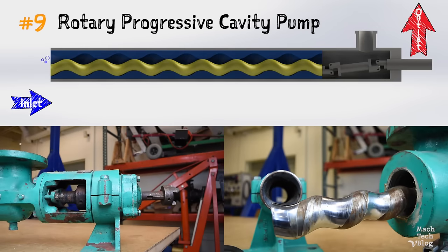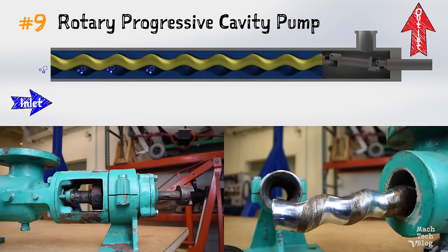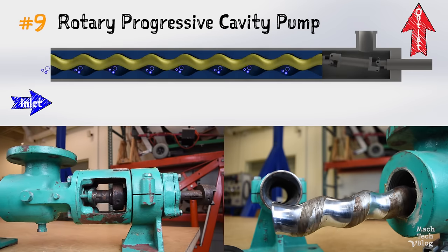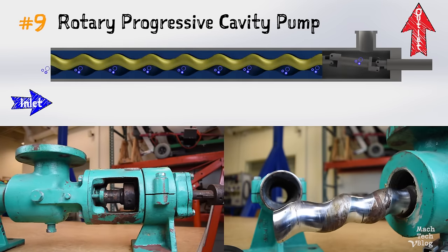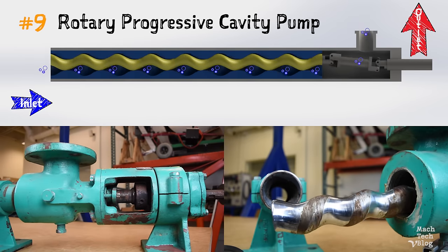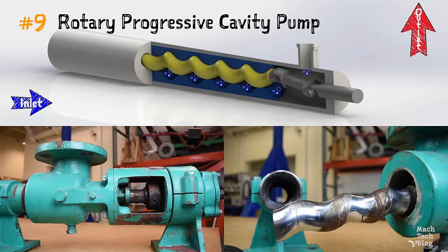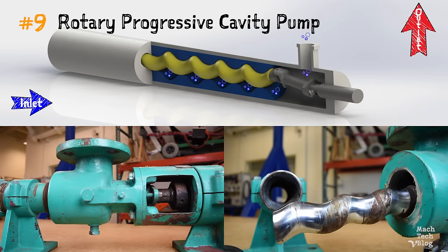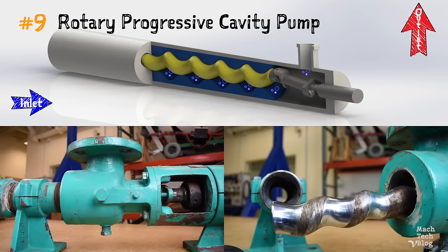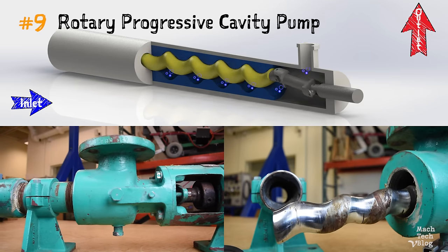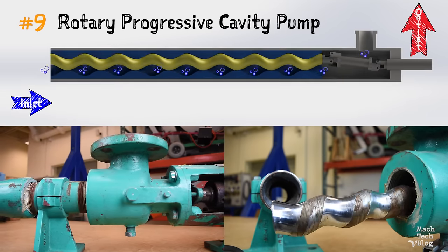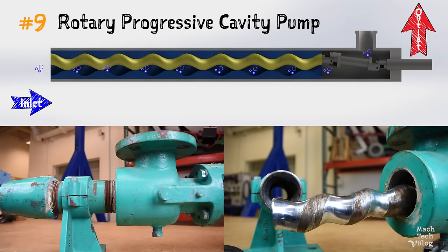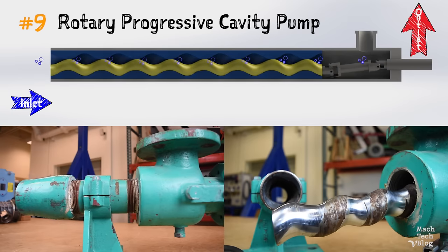Our final pump is pump number nine: the progressive cavity pump. These pumps may look somewhat like screw pumps, but they function differently. The rotor is shaped like a helix, and the housing is molded into the shape of a double helix. As the rotor rotates and oscillates inside of the housing, it forms a cavity which progresses along the length of the housing. Any fluid trapped in this progressing cavity is delivered to the discharge outlet.